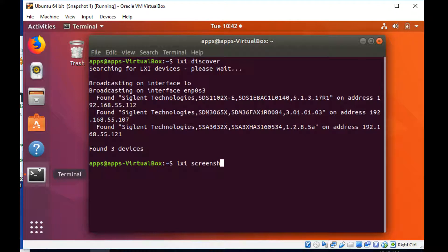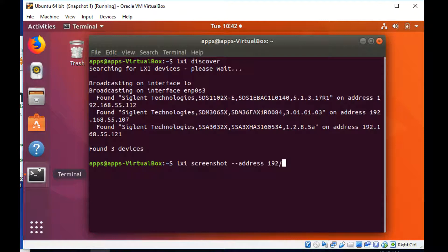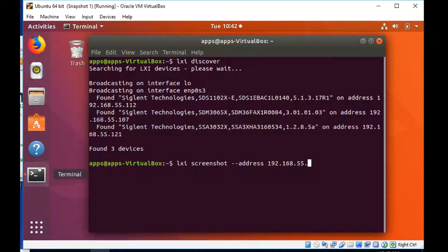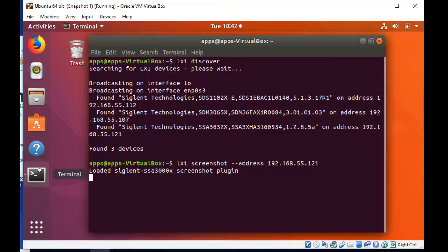We can also do a screenshot, which is just LXI space screenshot, and then the IP address for the instrument. And that's going to give us, I'm just going to type in the address to the analyzer, and that's going to quickly give us a screenshot of the analyzer.